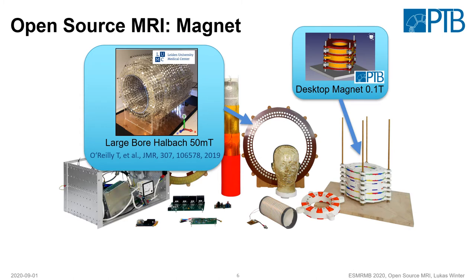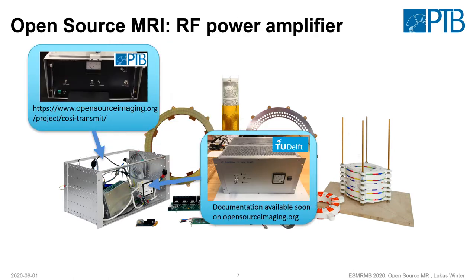Here are two examples for the magnet. In Berlin we are working on a small desktop magnet — 10 centimeter bore, around 3 to 4 centimeter field of view — and in Leiden there is a large bore Halbach magnet which was already used for head and knee imaging. We also have some RF power amplifier designs, one kilowatt peak power each. On the left is a design we did initially in Berlin, and here is a newer design by the Technical University of Delft where the documentation will be available soon.